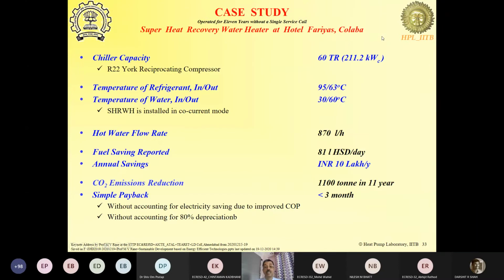Okay, and the payback, we had told them 6-month payback, but they actually got 2.86 months payback, and there is saving of about 1,100 tons of CO2 emission in the 11 years that they operated it. And the best part is when they scrapped the heat exchanger after 11 years because the chiller life of 20 years had passed, they got 5 lakh rupees as scrap value for the heat exchanger, while the actual heat exchanger installed was for 2 lakh rupees when it was initially deployed by my client. Okay, and of course the annual saving was as high as 10 lakh rupees per year because of the fuel cost going up. Daily fuel saving was around 81 liters of diesel.